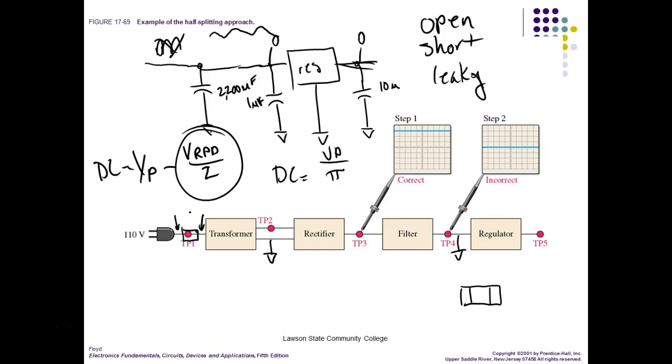But what if the fuse is good? Check the output of the transformer, yeah. So we come here and we do what? We measure the output of the transformer. So you need to know what that's supposed to measure. Of course, your meter is going to measure RMS. So we got 0 here, we got 0 here. We come over here and we measure this. If it measures 0 right there, and then I have on my primary, I measure something, and what's the problem?